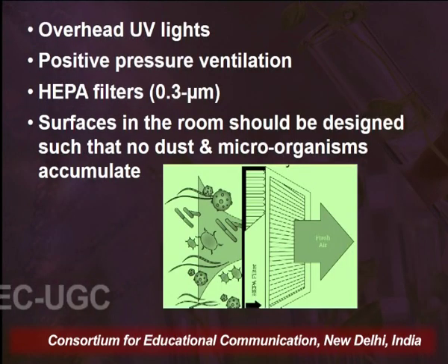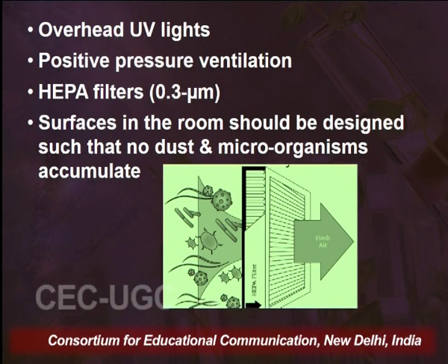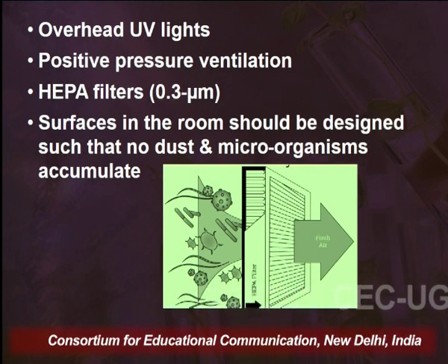It has also been found that overhead UV lights provide a sufficient amount of sterility in these transfer hoods or the transfer room. The transfer room should always have a positive pressure within the enclosed area. So whenever the door is opened, the air flows outside the room, and the outer air does not flow inside. Therefore, positive pressure always has to be maintained. As I discussed, the laminar or transfer hood should always be fitted with HEPA filters having a pore size of 0.3 micrometer, which prevents any kind of microbial contamination onto the media.